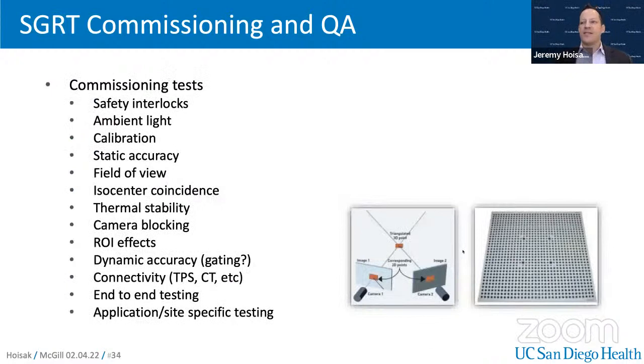Some commissioning tests when setting up an SGRT system include evaluating safety interlocks, evaluating ambient light conditions, calibrating the camera pods, evaluating their static accuracy, and quantifying the field of view. We have phantoms to measure isocentre coincidence, both with the linear accelerator, the surface imaging system, as well as the kV imaging systems.